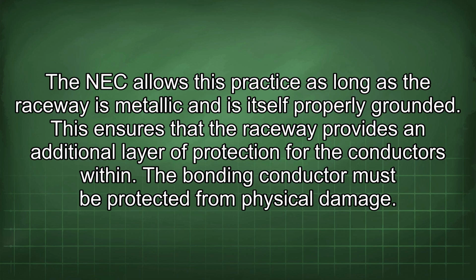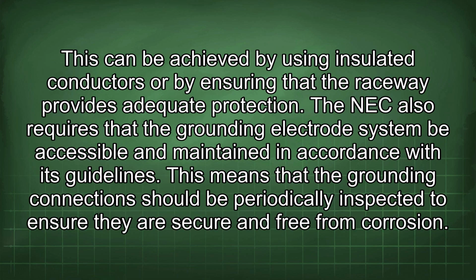The bonding conductor must be protected from physical damage. This can be achieved by using insulated conductors or by ensuring that the raceway provides adequate protection. The NEC also requires that the grounding electrode system be accessible and maintained in accordance with its guidelines. This means that the grounding connections should be periodically inspected to ensure they are secure and free from corrosion.